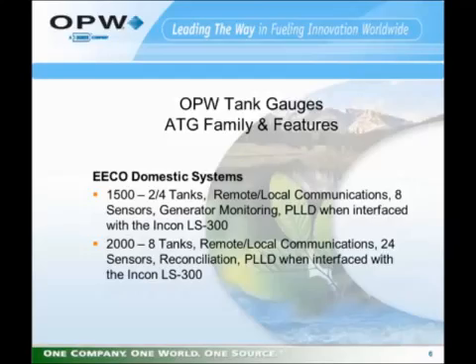The EECO 2000 has a capability of 8 tanks, remote and local communications. It will interface to up to 24 liquid sensors. It will provide inventory reconciliation when connected to fuel dispensing equipment, and it will also give you the capability of pressurized line leak detection when it is interfaced with the Incon LS300 pressurized line leak system.